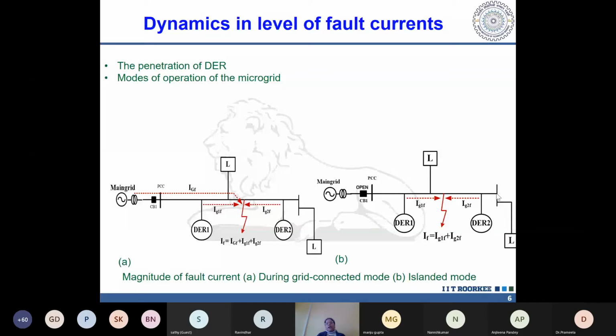Now in islanded mode, CB1 is open, meaning this breaker is open. So IF becomes equal to IG1F and IG2F, meaning the grid current is absent, so the grid side IGF is zero. This small example is just to help you understand mathematically what is meant by dynamics in fault current: the fault current level changes time to time.